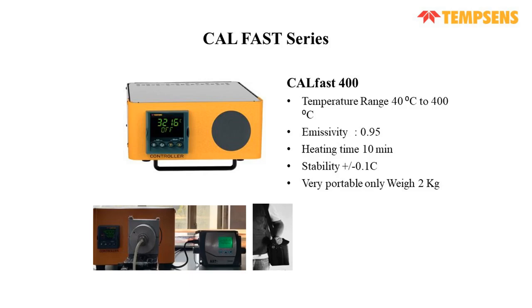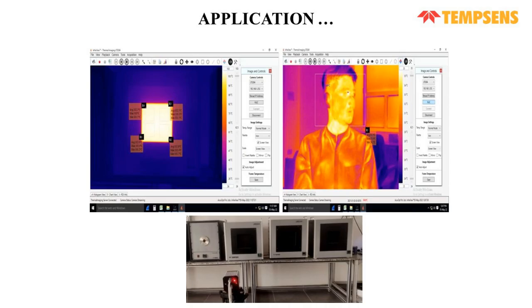Next, we have the Calfast series in Blackbody as well. It is called Calfast 400, and the temperature range is from 40 to 400, with emissivity of 0.95. The heating time is also very fast, 10 minutes, and stability is plus minus 0.1. It is again a very portable unit with weight just 2 kgs. These are the applications where Blackbodies come into picture: to calibrate pyrometers and to calibrate thermal imagers.